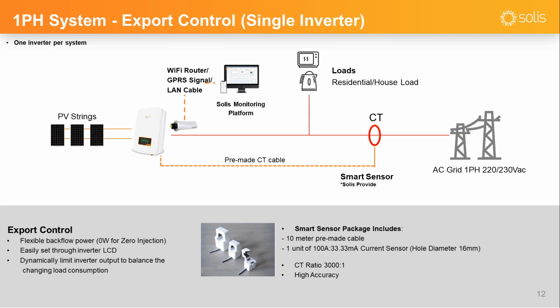then you can order either a CT model or a meter model. So if you order the CT model, then the model can connect the smart sensor using the pre-made CT cable provided by Solis, and then place the CT at the grid connection point of the system. And then that CT will measure the power flow at the grid connection point, and then backfeed the data to the inverter. So the inverter can dynamically limit the inverter output to balance the load consumption. So in that way, all generation will be used to support load consumption, and then we can guarantee there's no backflow power injecting to the grid, that is the zero injection scenario.